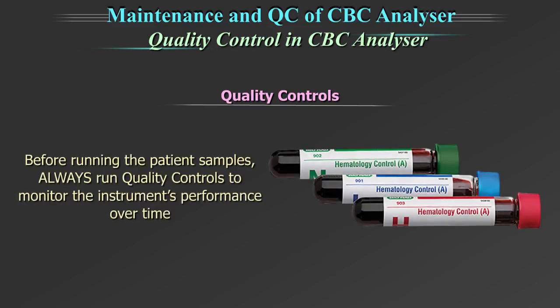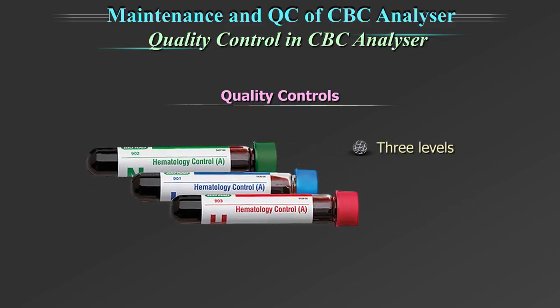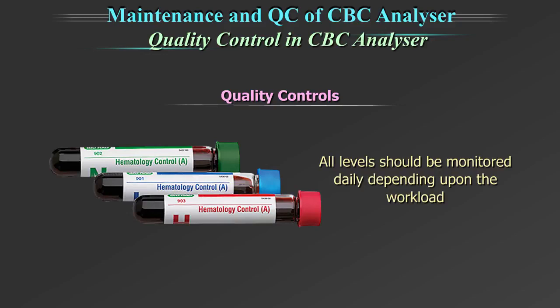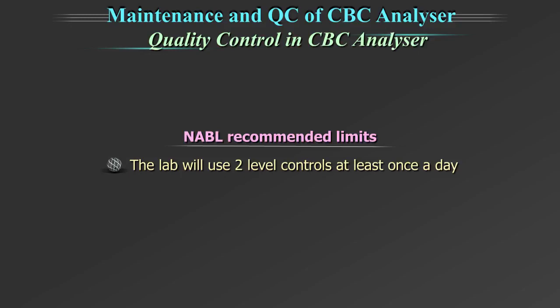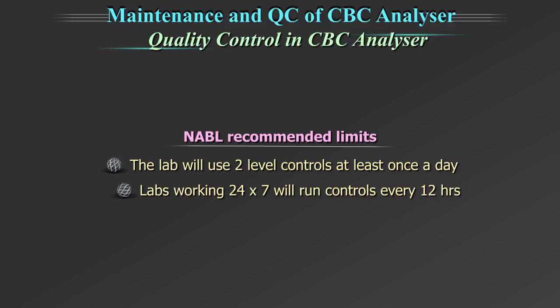Quality control. Before running the patient sample, always run quality control to monitor the instrument's performance over time. There are 3 levels of quality controls: low, normal, and high level to monitor different clinical decision levels. Ideally, all levels should be monitored daily depending upon the workload. The NABL recommended guidelines are: the lab will use 2-level controls at least once a day. Labs working 24/7 will run controls every 12 hours.